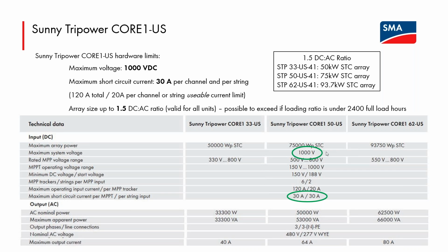Up to these limits, as long as the 2 values circled in green are being respected, you don't have to consult SMA at all. It's only going past these that we would run the design in Sunny Design, and then that full load hours metric must stay under 2,400. And what this is saying is the program is estimating that the inverter will be running at full capacity for no more than 2,400 hours in a year out of 8,670 for the year, or 8,760, I think I'm switching the numbers around. So a fair number of hours per year that the system would be under full load.